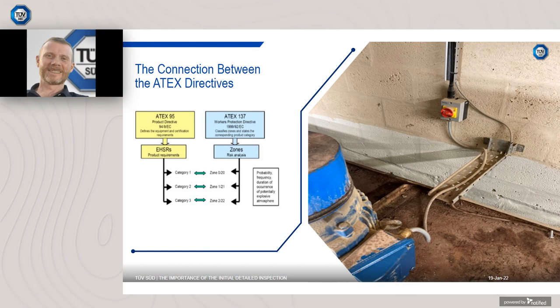Connection between the ATEX directives. This diagram shows the integration between the directives. The user directive classifies the zones and identifies which product category can be used in each zone. The equipment directive certifies the equipment design against the essential health and safety requirements for each category of protection. Zones define the probability, frequency, and duration of the occurrence of a potentially explosive atmosphere. Categories define the level of EX protection required.